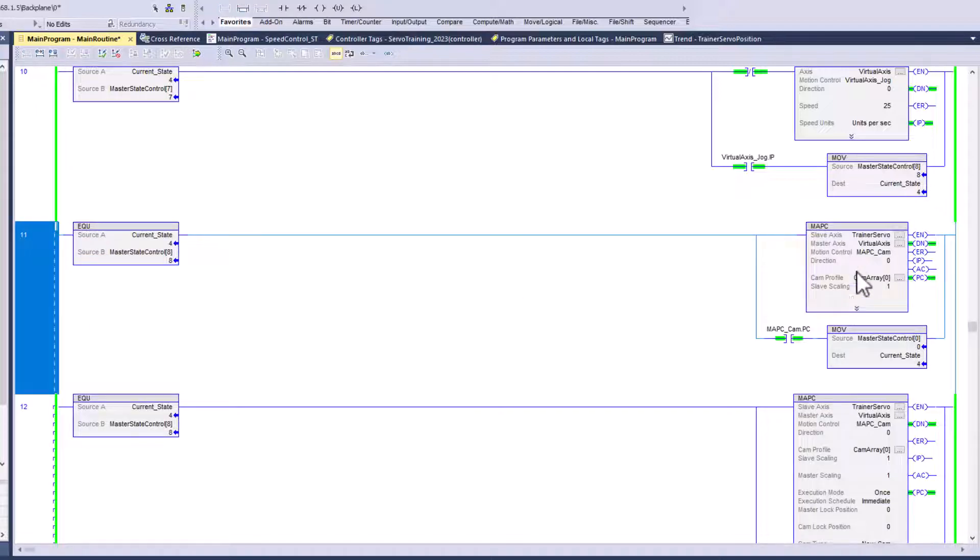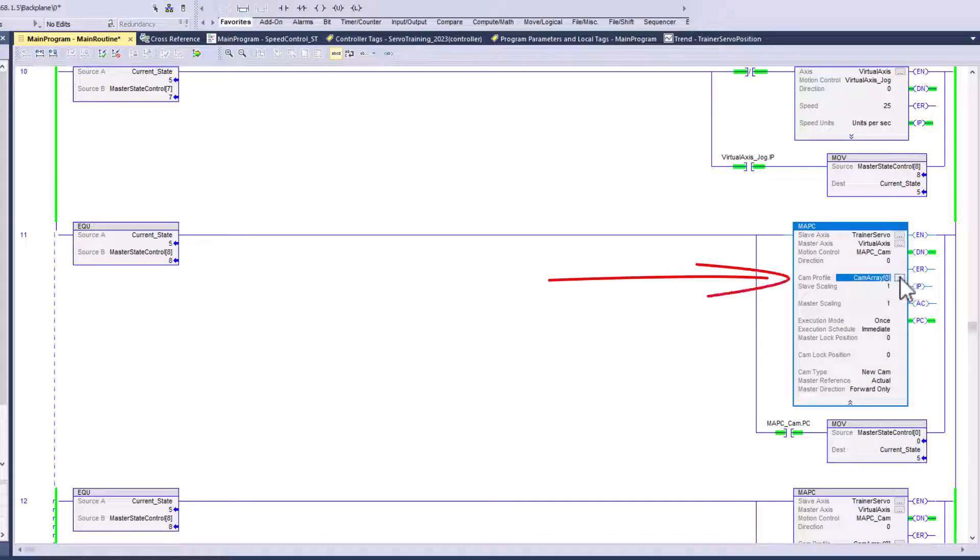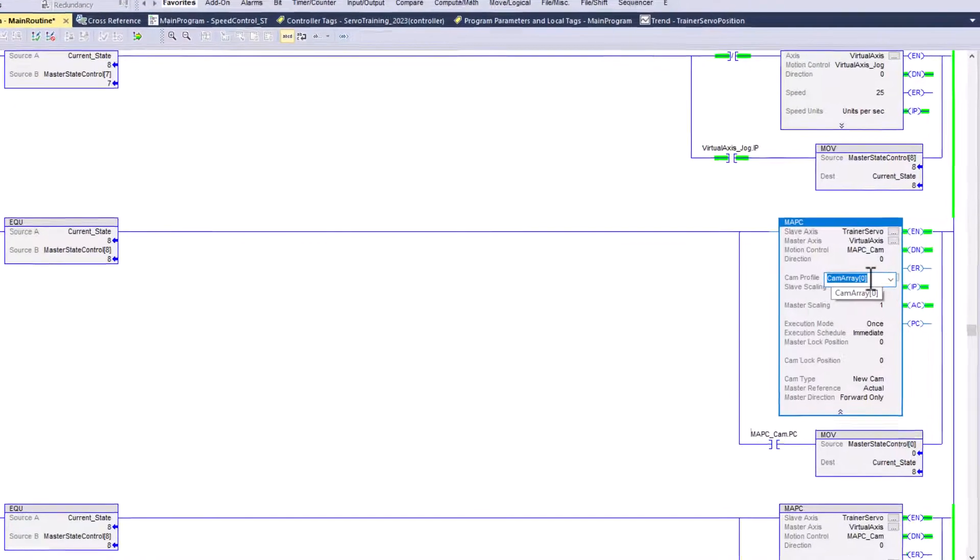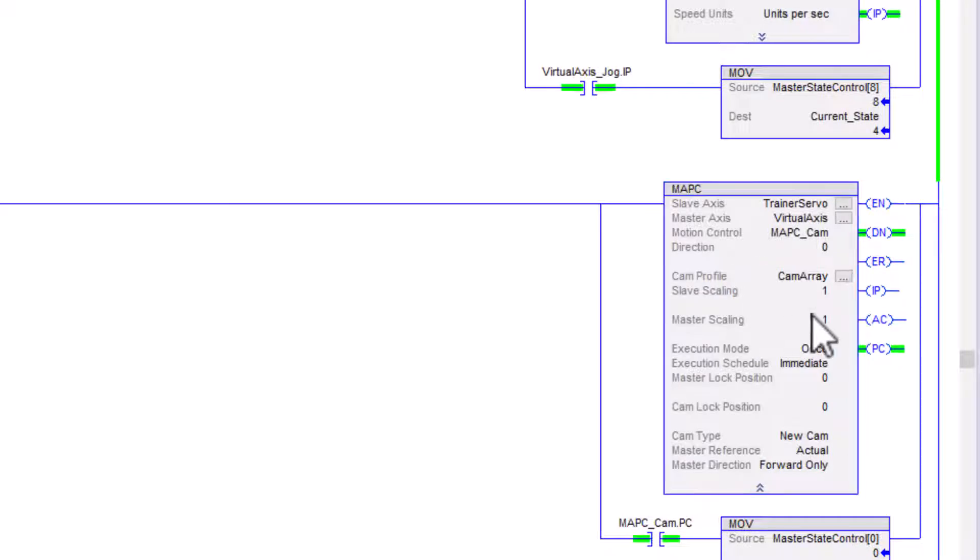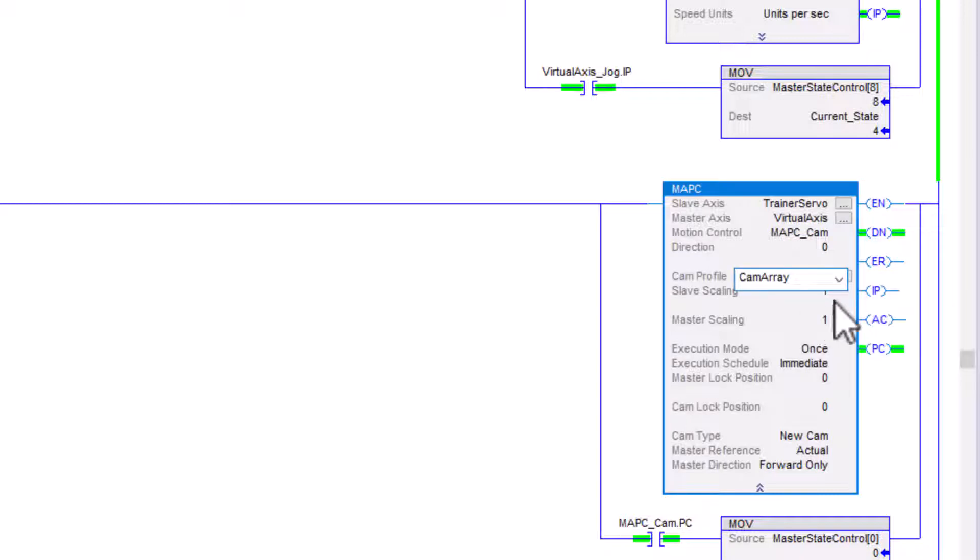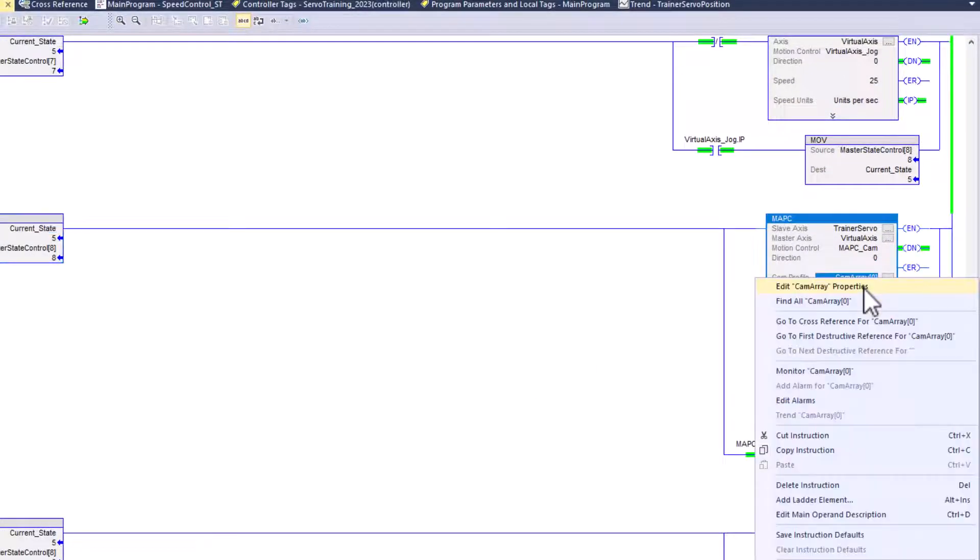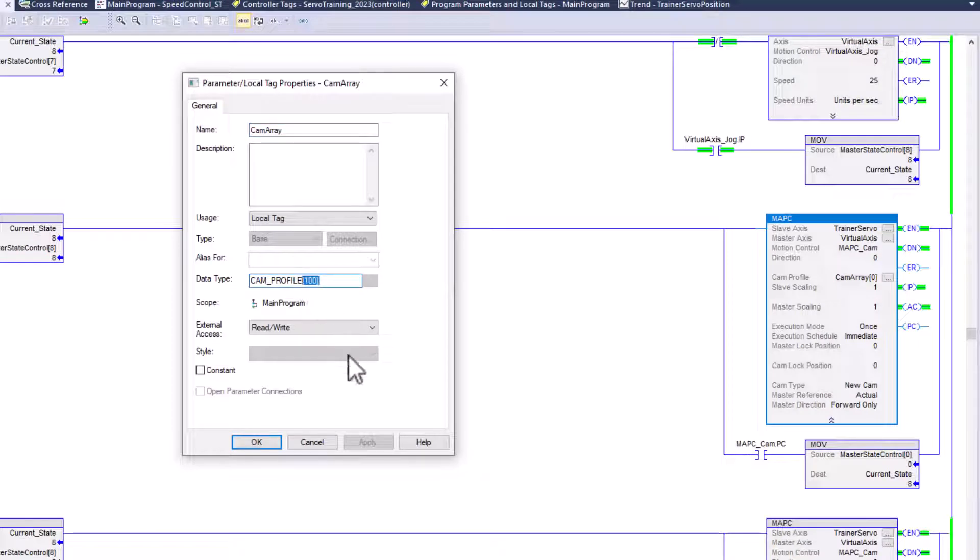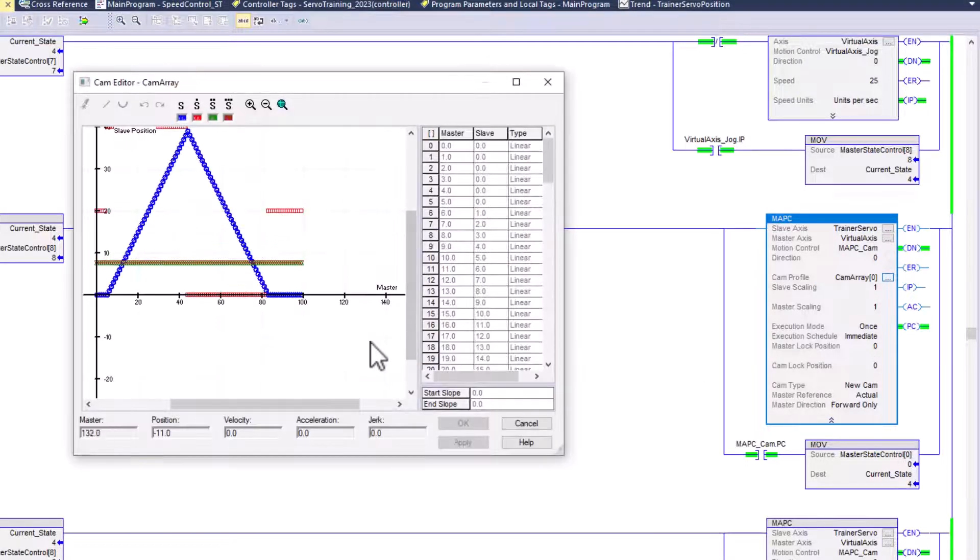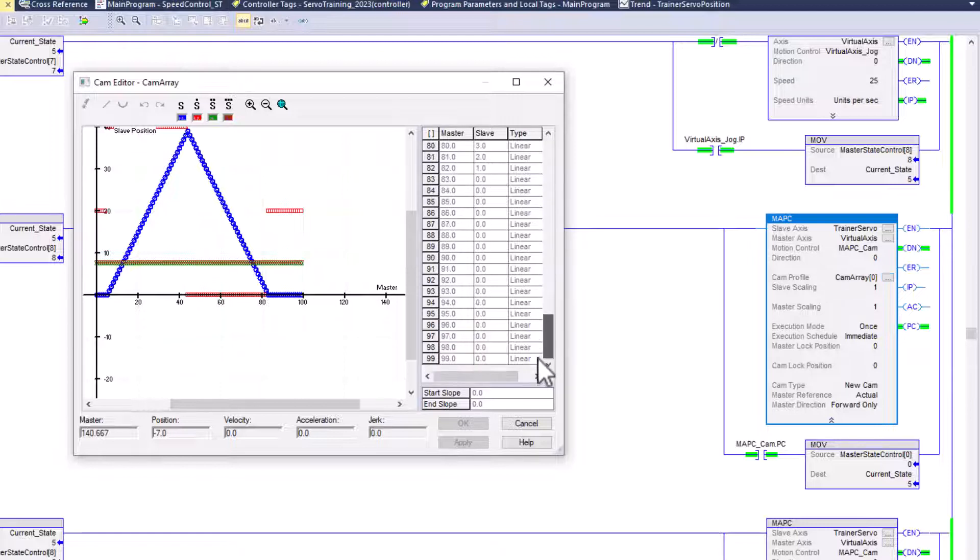First, I want you to understand right here, when you do a cam, like when you start your cam profile, you see how mine says it's cam array and it starts at the very first element. So let's just say you took that out. Then that could potentially cause a problem. So the best practice is always to select the very first portion of the cam that you're using. Now in my case, my cam profile is 100. So I only have 100 points, which you can see right here. If I pull my cam profile up...